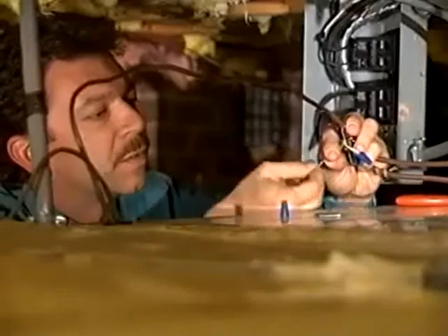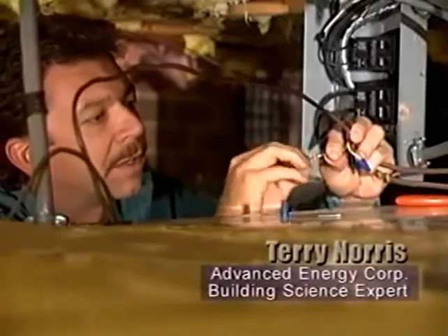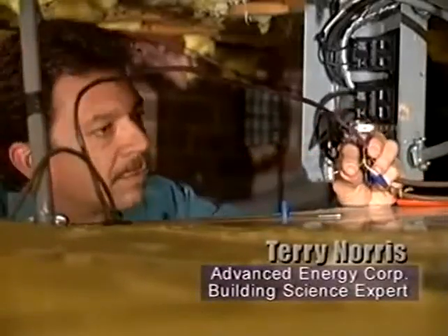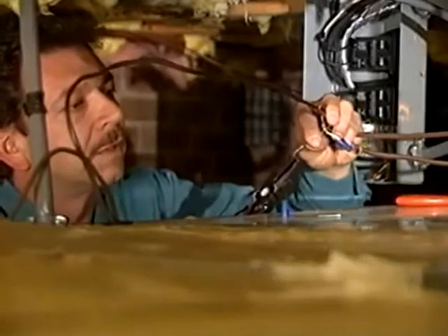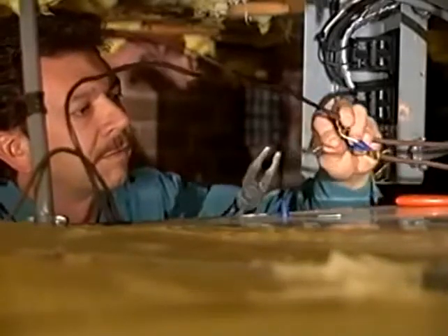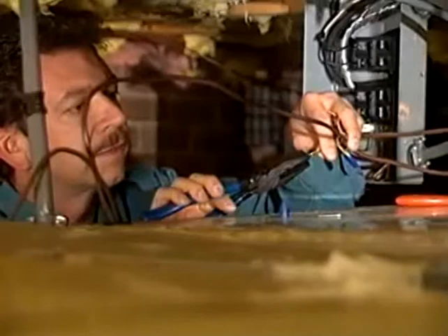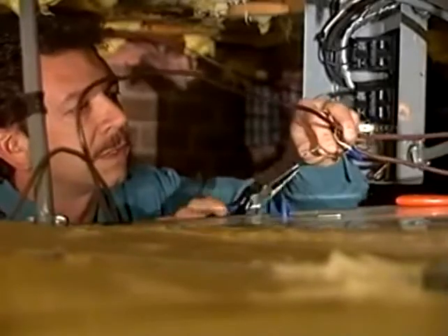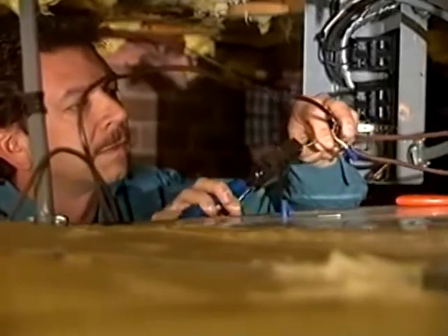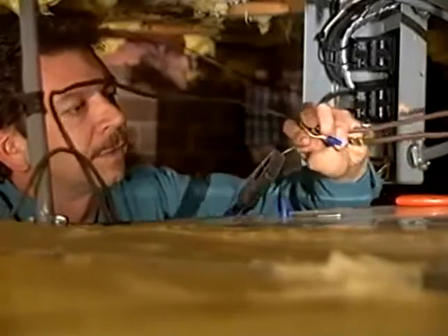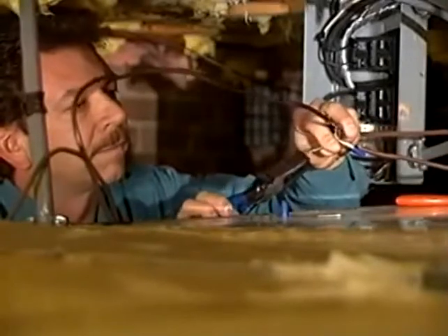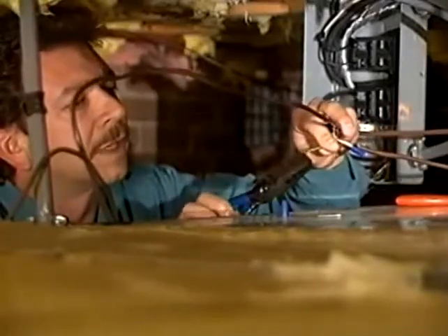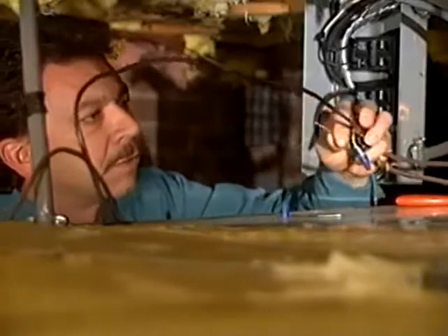One of the important things in wiring low voltage is to twist the wires before you put the wire nut on, anytime you're going to use a wire nut. The wire nut is used just as a cover for the wire. The actual connection is made through the twisting of the wires. If you just put the wire nut on, you're going to have a loose connection, and that could cause your relays and contactors to burn up.